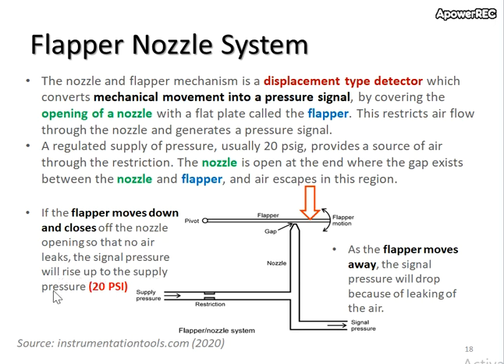The signal pressure will rise up to the supply pressure, which is 20 psi, meaning the signal pressure will be equivalent to the supply pressure. But if the flapper moves away from the nozzle, the signal pressure will drop because of the leaking of the air.